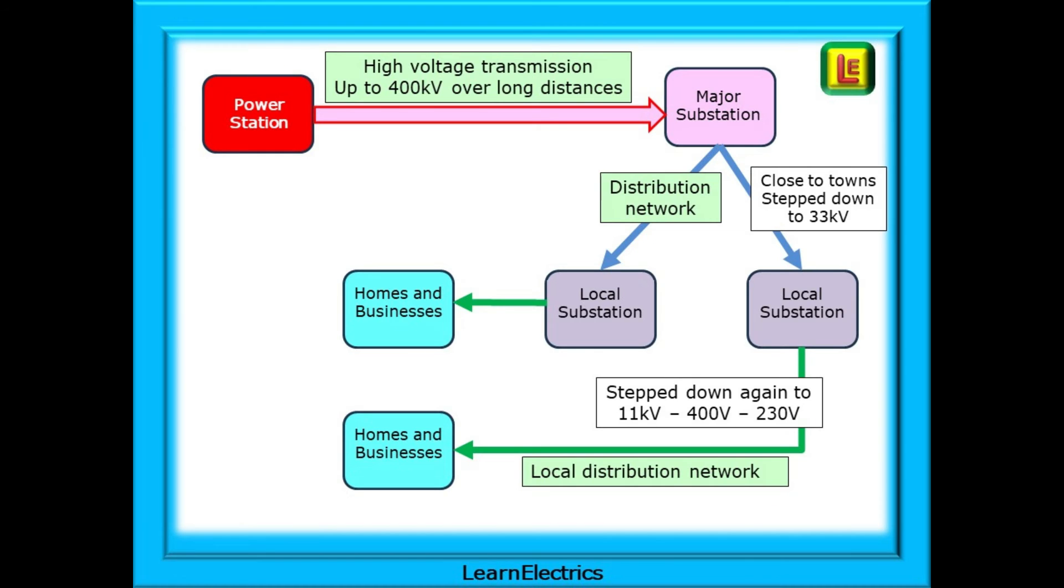This is the basics of how it works then. The power station outputs electricity and this is stepped up to 400,000 volts for transmission over long distances, many, many miles. At various points at major substations, the voltage is stepped down to around 33,000 volts and then distributed to local substations. There may be one in a small village, several in a town, and hundreds of local substations in big cities. The voltage is stepped down and distributed to homes and businesses in the local area as a usable 230 volts or 400 volts.